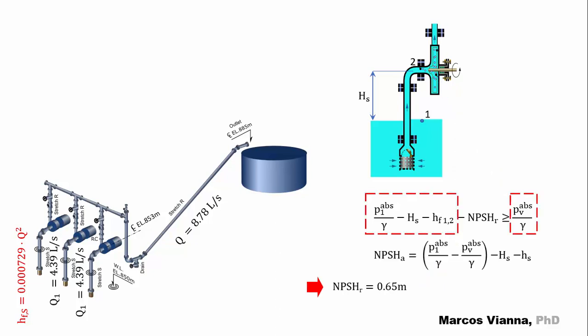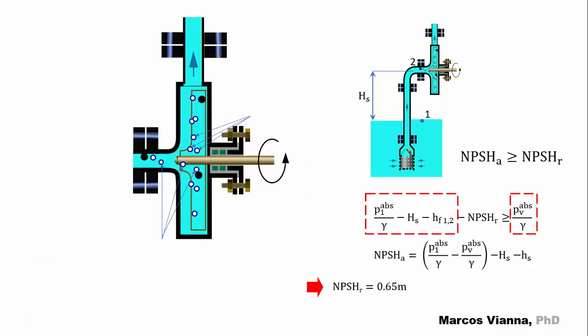This is what we call available NPSH. It's the absolute net head that we deliver to the pump. Of course, it must be greater than the required NPSH or vapor cavities will form inside the pump, bringing all the terrible consequences that we must avoid. There's a specific video in this channel about this topic. I'll leave its link in the description.